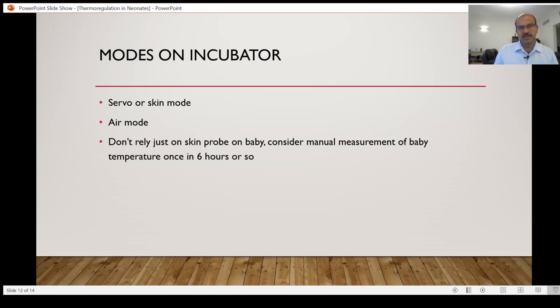Don't confuse it — the skin mode also heats the air in the incubator, so the measured air temperature is the actual air temperature the baby needs in the environment. The skin temperature is measured by the probe, for example on the left-hand side in the Giraffe incubator. You compare the temperatures, switch the baby to air mode, keep the temperature at the same level, and gradually reduce it. You would find the baby maintains at around one degree less after a few days. This difference matters because increased heat affects the metabolism — the basal metabolic rate is higher, just like hypothermia is harmful.